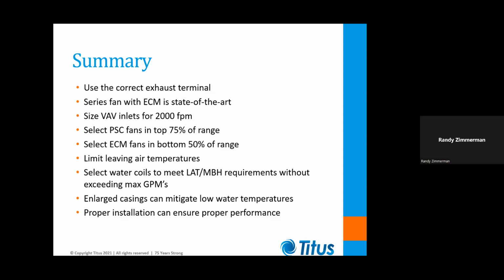We want to limit our leaving air temperatures usually to no more than 90 degrees for overhead heating. We want to select our coils to meet the leaving air temperature or MBH requirements without exceeding the maximum GPMs by too much. We also want to deal with low water temperatures by using enlarged optional casings on our units. And we always want to install the units properly to ensure proper performance.